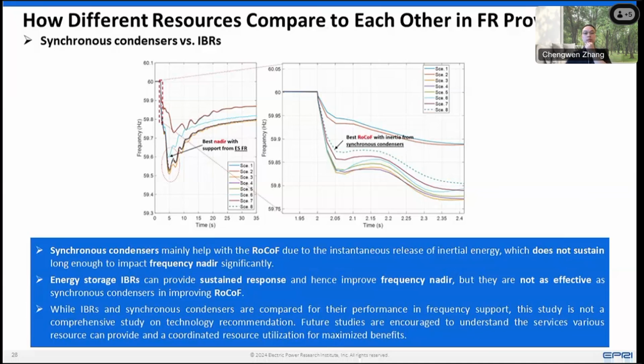On the other side, the IBRs were not as effective as synchronous condensers in limiting the RoCoF, because they don't have the absolutely instant response of physical rotating mass. But they are very effective in arresting the frequency nadir. If you look at the blue curve on the left, that's the IBR providing faster frequency response—it actually provides a much better frequency nadir than synchronous condensers.